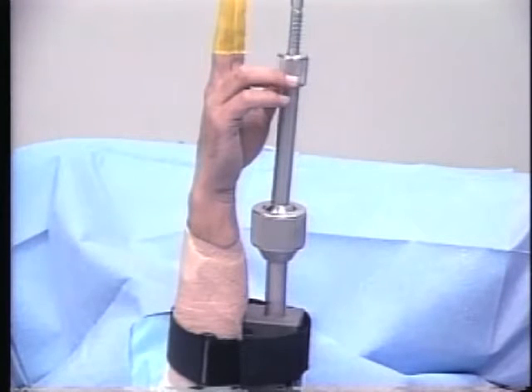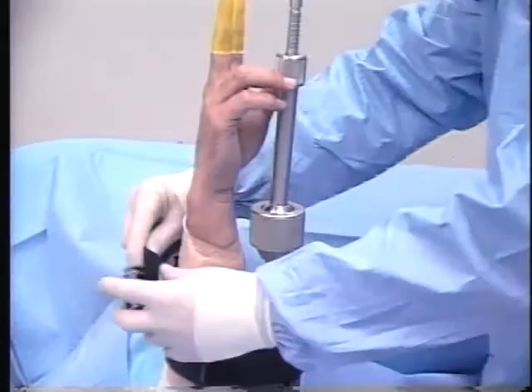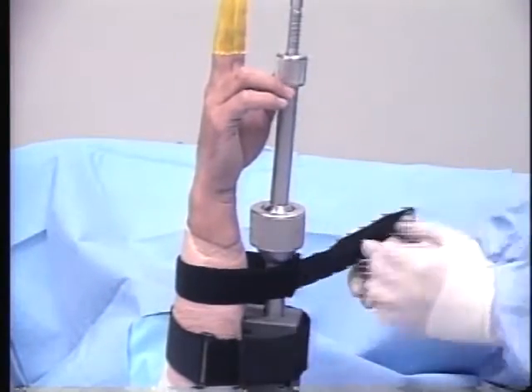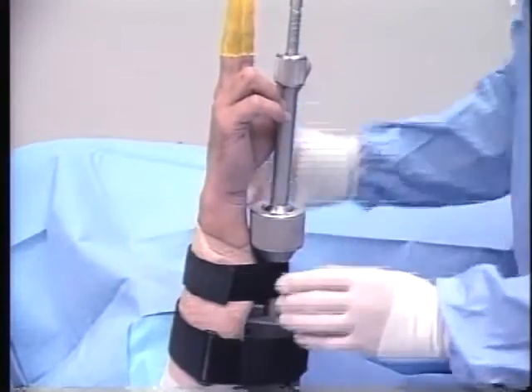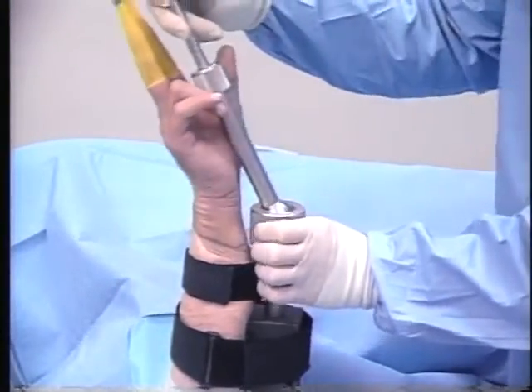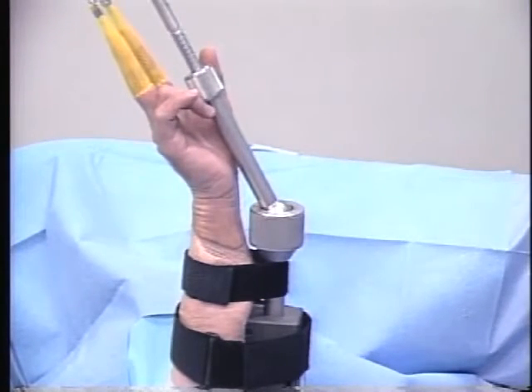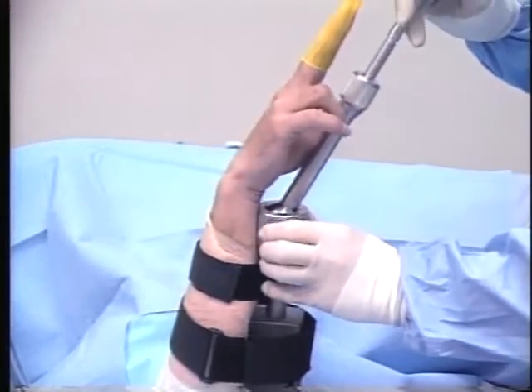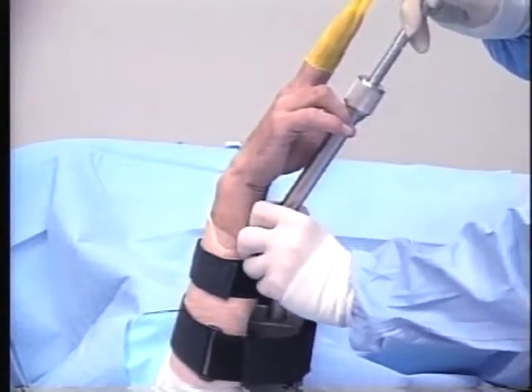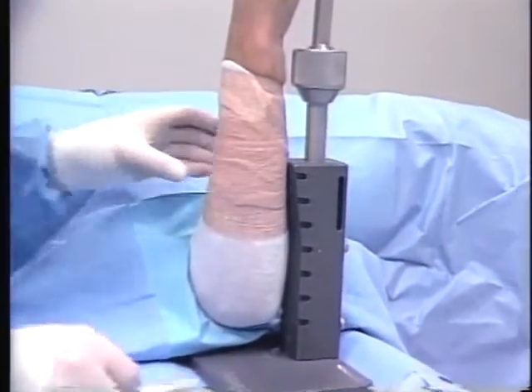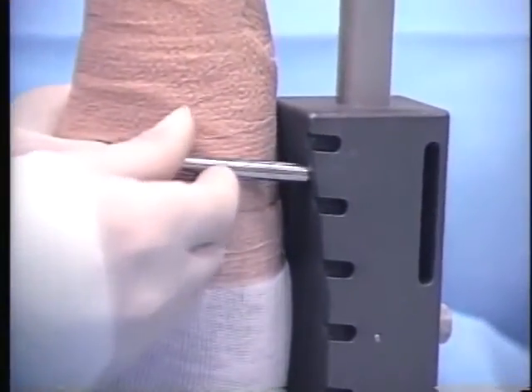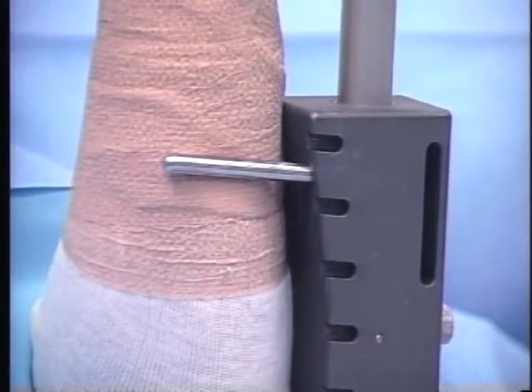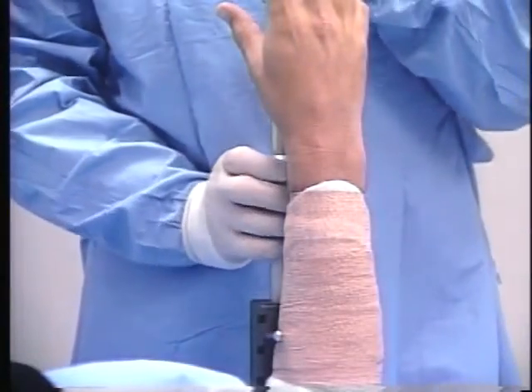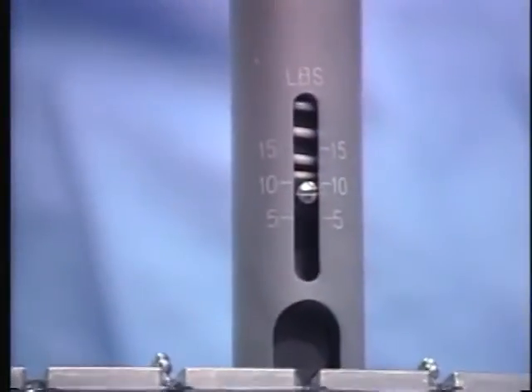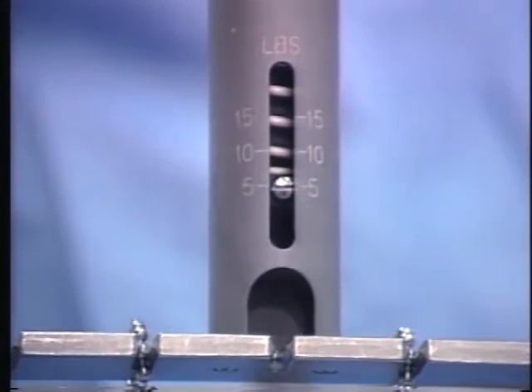The wrist is stable in a vertical position and several options are available. A wrist strap can be added for additional stability. The ball joint can be loosened with a counterclockwise twist to allow wrist flexion, extension, or radial ulnar deviation. To facilitate radial or ulnar deviation, the radial ulnar deviation pin can be placed in the appropriate cavity of the primary support to counteract the pivotal forces. It's important to note that moving the upper portion of the traction tower to alter wrist flexion, extension, or radial ulnar deviation will affect the traction force being applied.